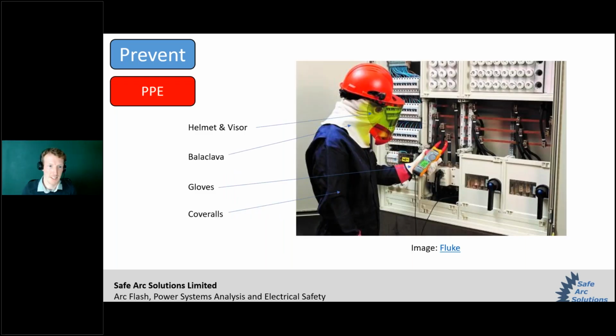With Arc Flash, you tend to find that there's always some residual risk. And so Arc Flash PPE is more often than not adopted for activities on or around live equipment. Arc Flash PPE is primarily there to mitigate against the thermal effects of the Arc Flash, and it's available from a number of different manufacturers. What it typically comes with is a rating helpfully given in calories per centimeter squared, which is a number determined through laboratory testing.